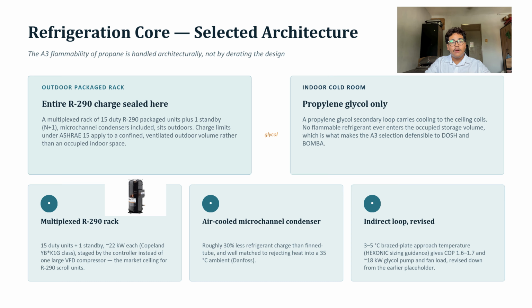You will notice we also use a rack system instead of one large compressor. The largest single R290 scroll compressor on the market, the Copeland K1G class, tops out at roughly 22 kilowatts. Therefore, our rack utilizes 15 duty units plus 1 standby for redundancy. Each unit is paired with an air-cooled microchannel condenser, which requires roughly 30% less refrigerant charge than a fin-tube design and performs optimally in 35-degree ambient.